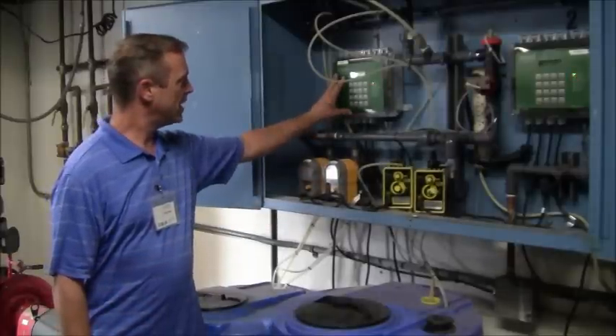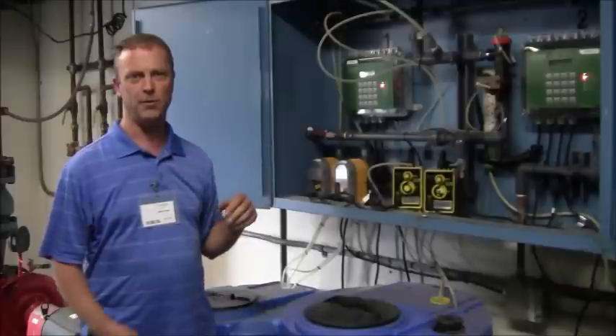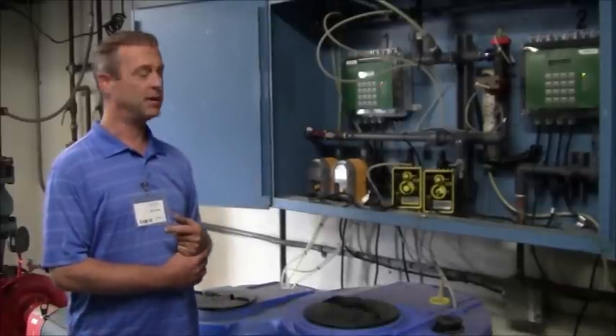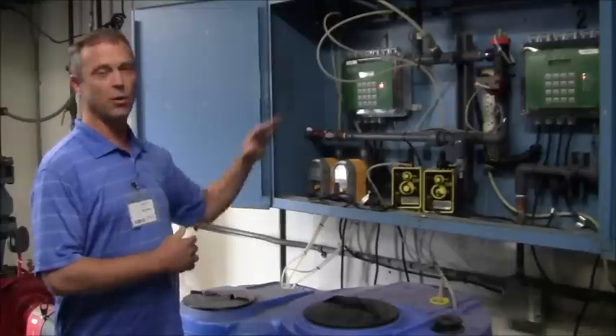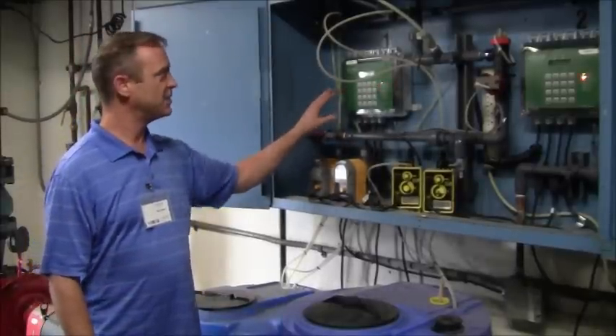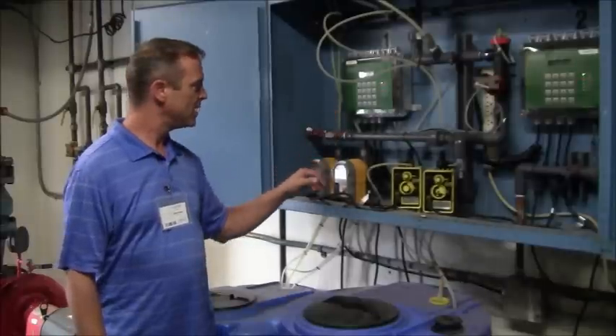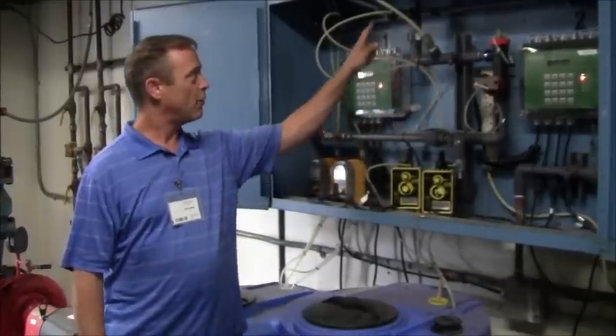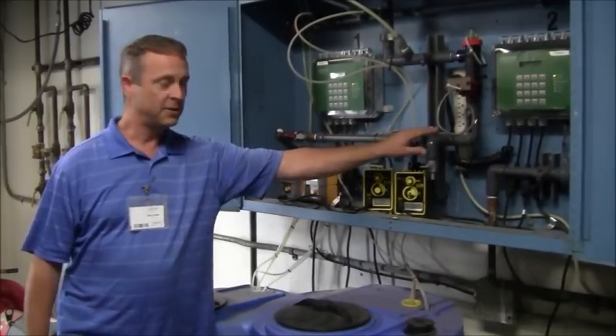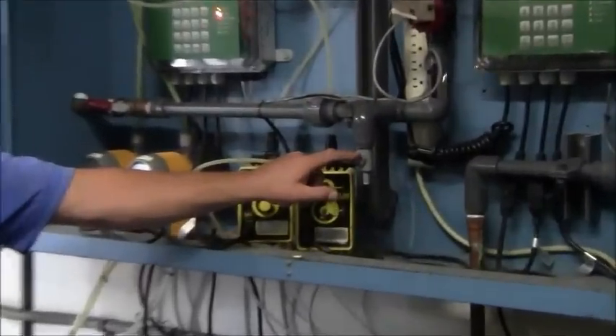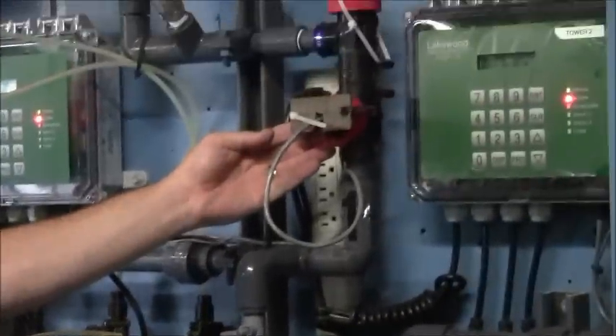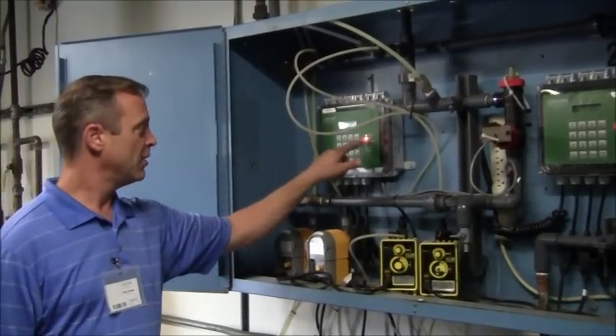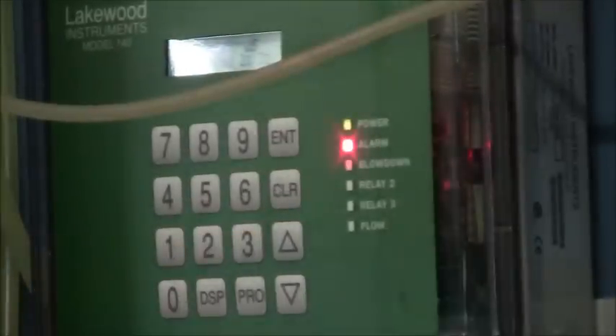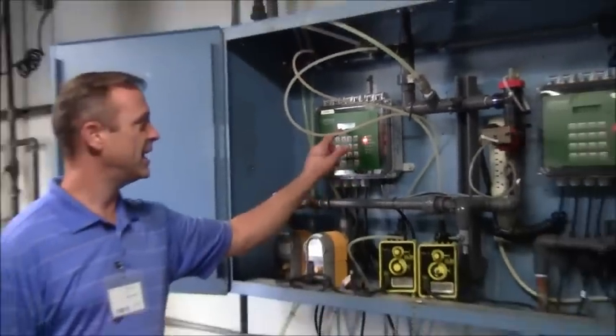This is basically your conductivity controller. This happens to be a Lakewood model, but there are a plethora of models on the market. So we won't go into detail about how this operates. They're all basically the same at this level. You're going to have a sample stream of tower water coming through the system here. We typically like to have a little sample petcock where we can grab a sample. This would be your conductivity probe that's basically monitoring and giving you a display readout all the time. Currently you'll see that it's flashing red. We're not scaling up the plant right now.